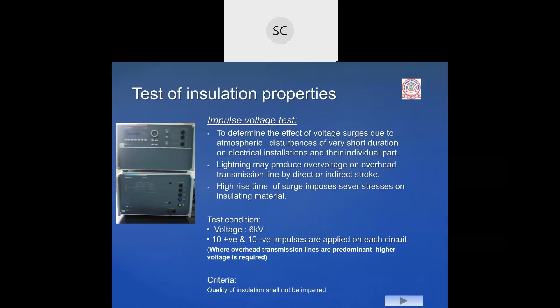If it is an insulated body, as nowadays all meters are polycarbonate meters, we have to wrap the meter with a copper strip, and then apply the impulse between these two. This is the stress. If the auxiliary supply voltage is less than or equal to 40 volts, we need not test. The test is not applicable if the auxiliary voltage is less than 40 volts.